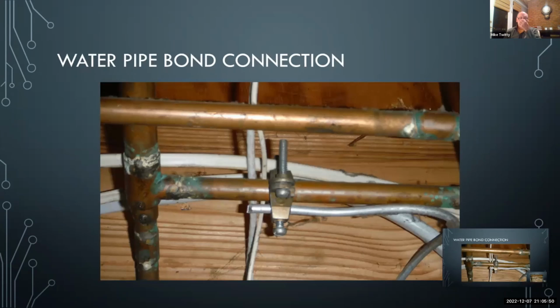Okay, water pipe bond connection. This is different from the grounding. Let's say you've got an older house that's all metal piping, copper or galvanized back in the day. That's all your distribution piping in the house, and the service line has been changed to PVC or PEX, more likely PEX. The water piping in the house still has to be bonded, because if an energized wire gets on that, it electrifies your distribution plumbing. So this is a water pipe bond.